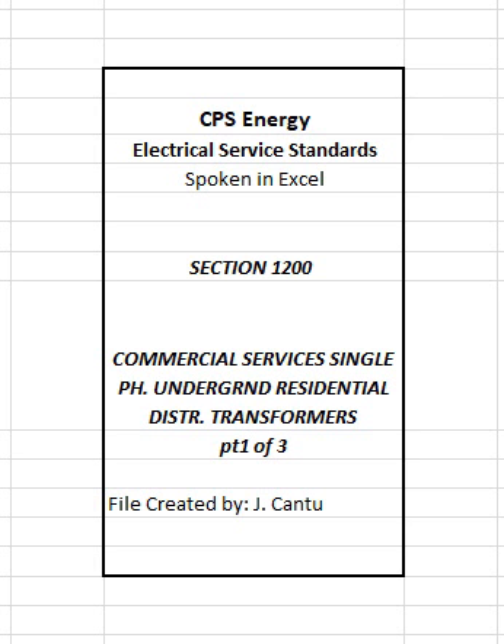1203 CPS Energy Job Sketch. A customer requesting service from a single-phase pad mount transformer shall make arrangements with the CPS Energy customer service representative. When all requirements have been met, CPS Energy will issue the customer a detailed construction sketch for the construction of the transformer slab, associated primary, secondary, and service trench detail and conduits as applicable. 1204 Standard installation. A standard single-phase URD pad mount transformer installation will typically consist of the following.